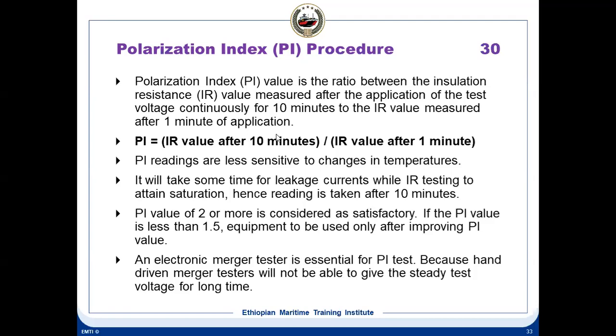So PI means the IR value after 10 minutes divided by the IR value after 1 minute. That becomes your PI, the polarization index. PI readings are less sensitive to changes in temperature. That is the advantage of PI readings. They are much less sensitive to temperature, whereas the insulation resistance test is very sensitive to temperature. With every 10 degrees centigrade, your insulation value can change, but the PI value does not change.